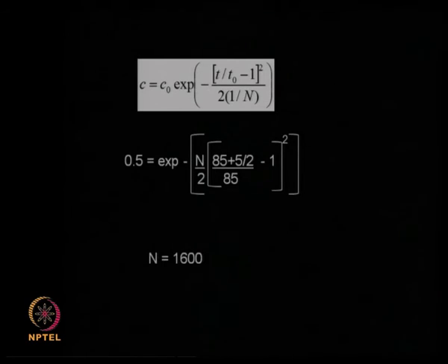Why is it so important? This number of theoretical stages or number of theoretical plates is very important because it tells you the quality of the chromatographic column. Higher the stages, that means better will be the resolution and better will be the separations, and sharper will be the peak. So the Gaussian peak will have a very good sharp appearance. So if you have multiple solutes present, the overlap of these solutes will be minimal. So that is the main advantage.